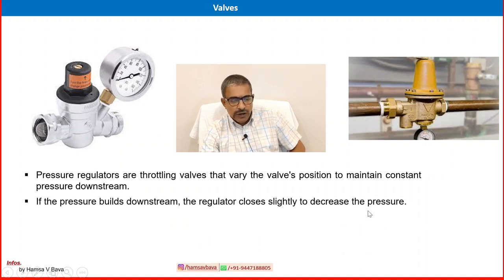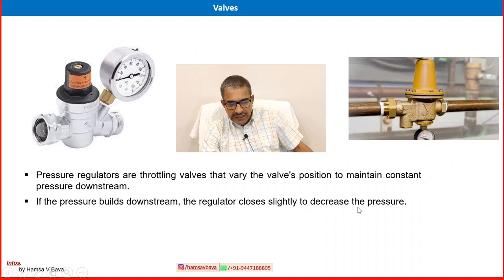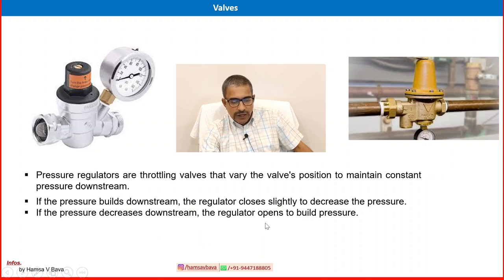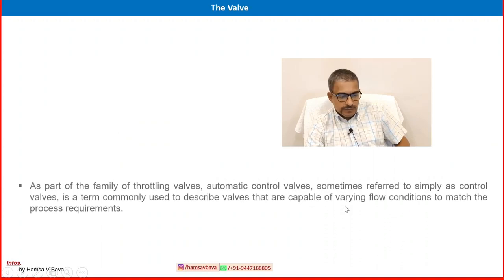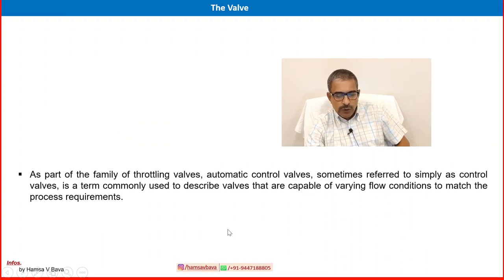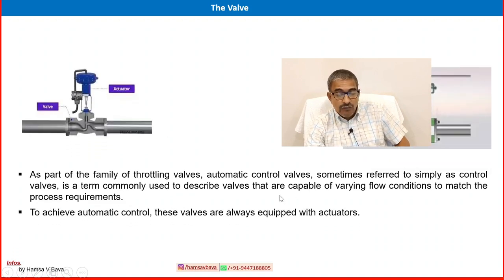One important application is just before a control valve, and another important application is in pneumatic actuator-operated control valves. If pressure builds downstream, the regulator closes slightly to decrease the pressure. If pressure decreases downstream, the regulator opens to build the pressure — automatically throttling to maintain downstream pressure. Control valves are the most common example of throttling valves, sometimes referred to simply as control valves, which continuously vary flow conditions to match process requirements.